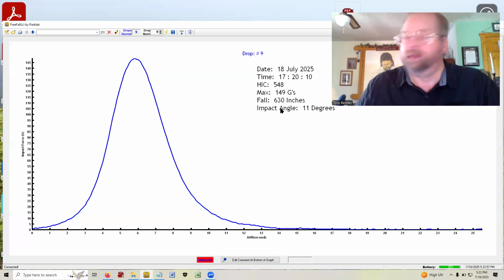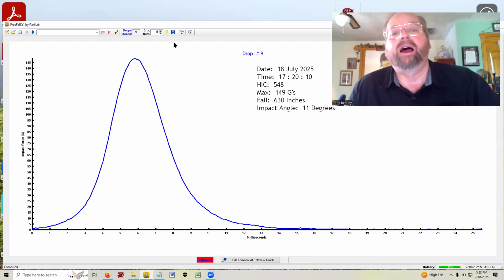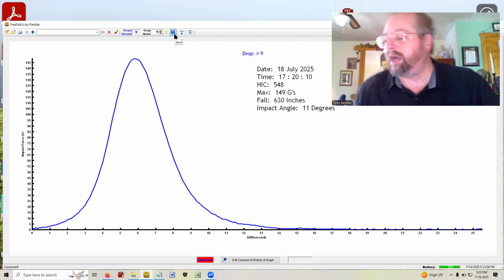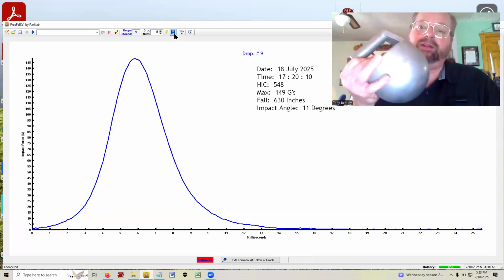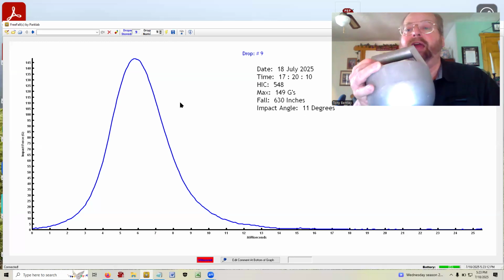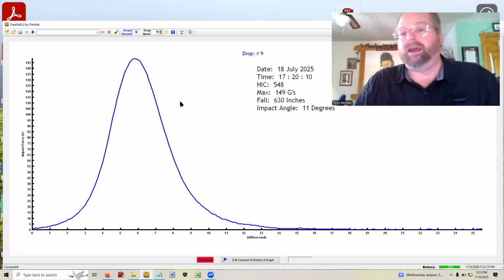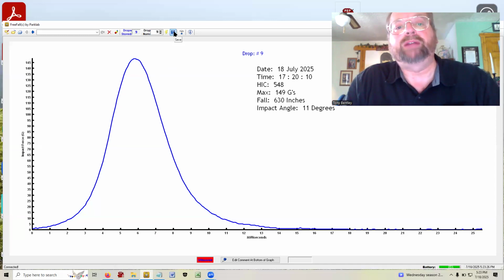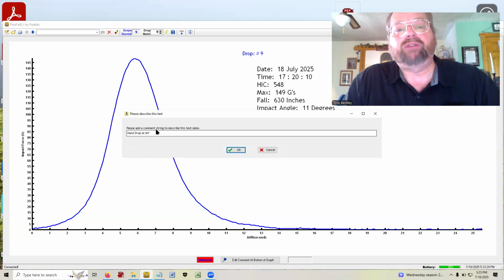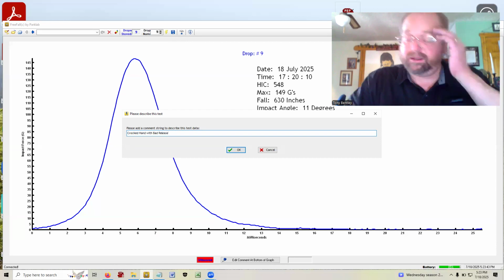So I purposely made this a bad drop, but you should save your data on your laptop. Right now, the data is downloaded to the laptop, but it's not saved in the laptop. And you don't want to just leave them in the FreeFall device because if your battery goes completely dead, you might lose some data. So you want to save all the important data on the laptop. I'm going to show you how you do that. You press the save button, and it's going to ask you for a description. So this was a crooked hand drop with bad release. Okay, that's why it was a bad release. That's why the fall height was drastically wrong.